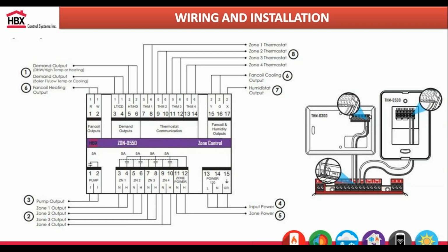We also can control your main system pump. And like I mentioned before, your air elements are on the top of the zone controller. So you can control your R, W, Y, and G's to make a heat call for your fan coil or furnace, make a Y call to your air conditioner unit or a cooling call to your fan coil unit, and G to run your fan. We can run that fan manually on, off, or intermittently, so you have the option to control different fan options. And then again, you can hook up your humidifier or dehumidifier to the X terminal.